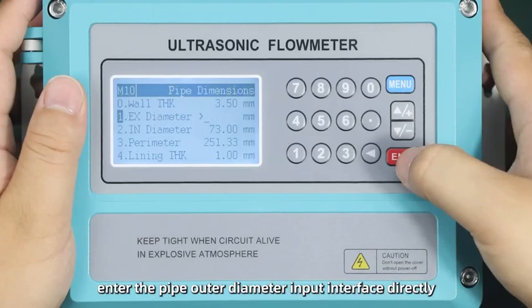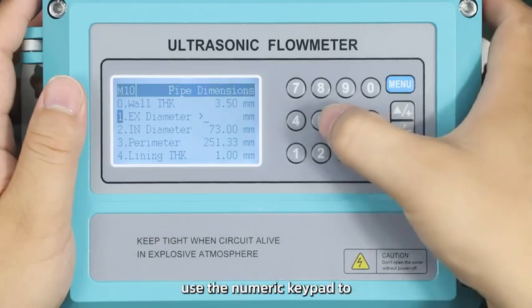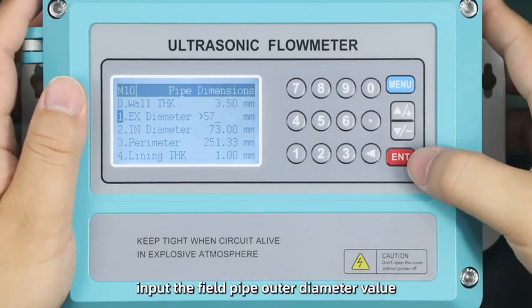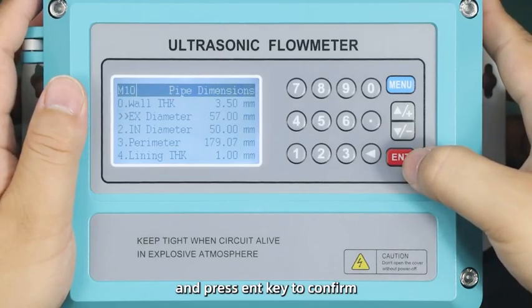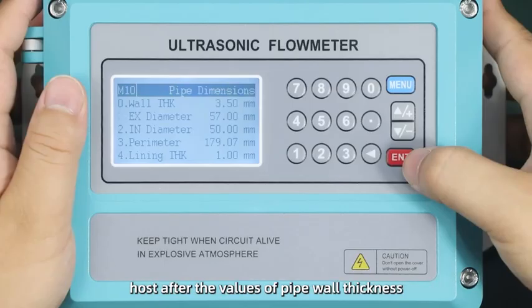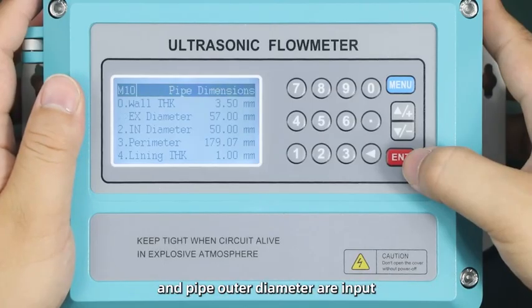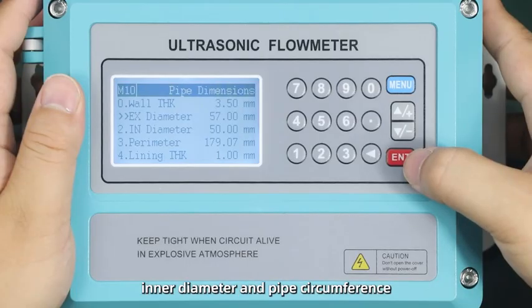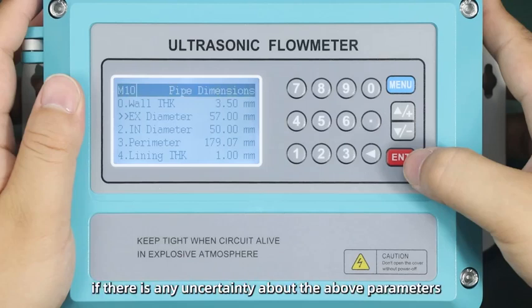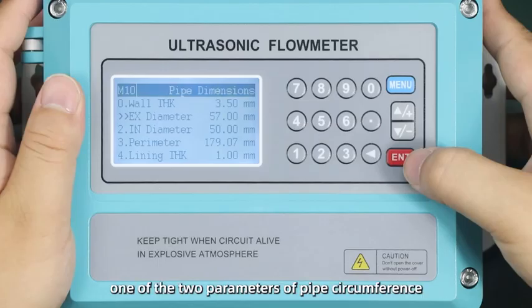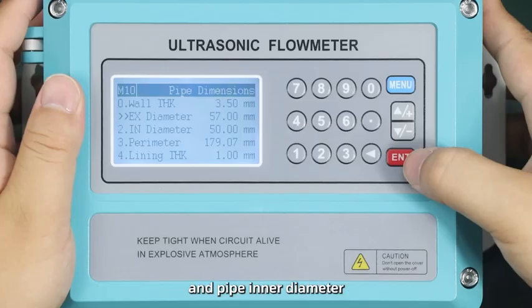Press the ENT key, enter the pipe outer diameter input interface. Directly use the numeric keypad to input the field pipe outer diameter value, and press ENT key to confirm. Due to the built-in conversion program of the Flowmeter host, after the values of pipe wall thickness and pipe outer diameter are input, the values of pipe inner diameter and pipe circumference will be automatically converted by the host without modification. Similarly, if there is any uncertainty about the above parameters, you can determine one of the two parameters of pipe circumference and pipe outer diameter, plus one of the two parameters of pipe wall thickness and pipe inner diameter, and enter two confirmed parameters, and the other parameters will be automatically converted by the host.